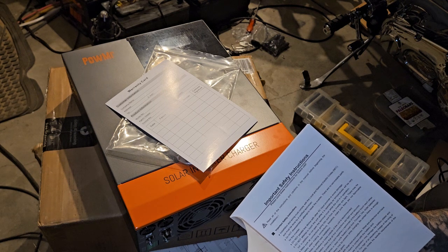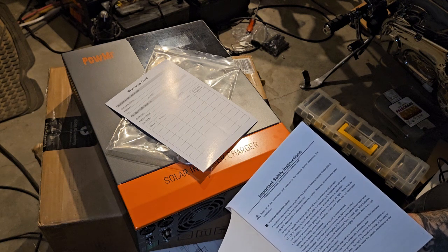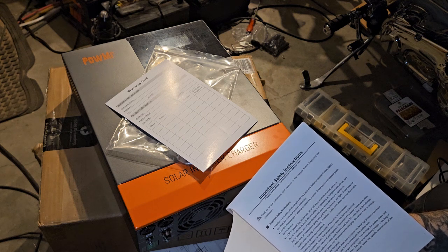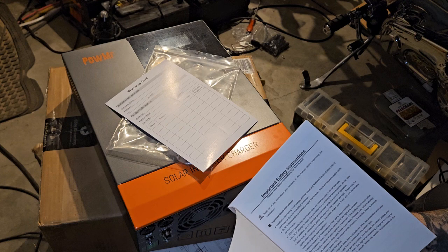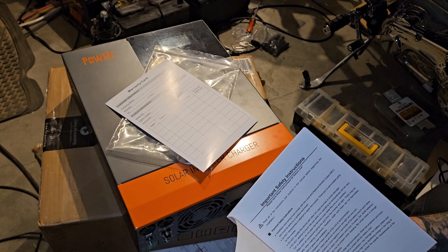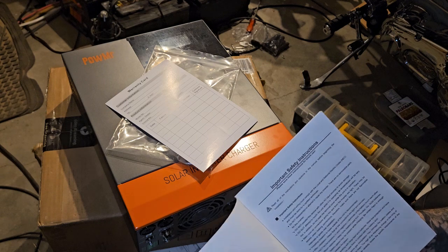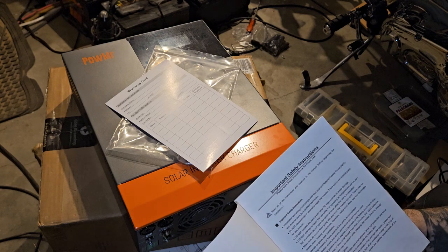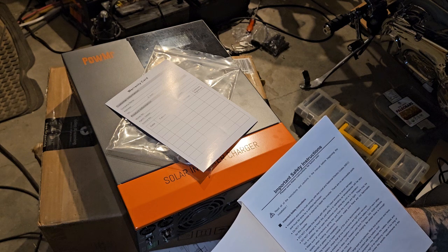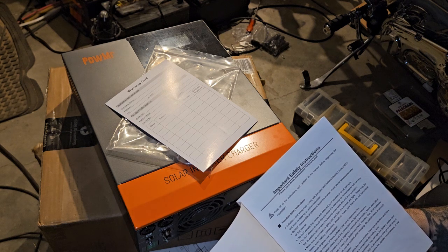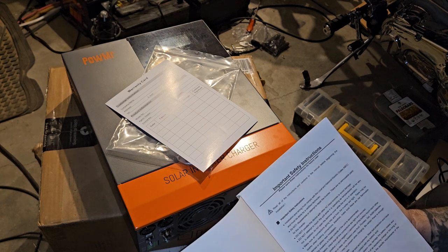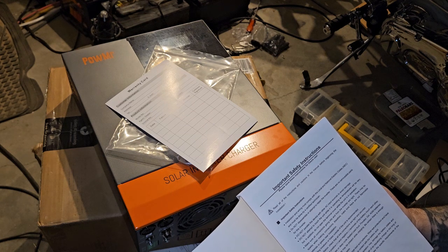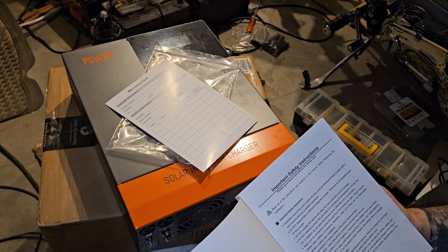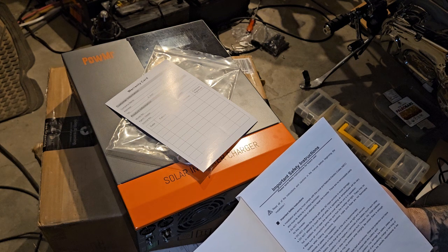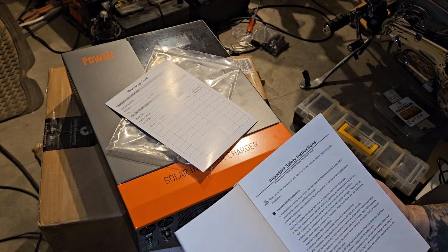Do not disassemble or attempt to repair the inverter. Do not parallel. Do not attempt to touch the unit while it's operating, as temperatures will be very hot. Lovely. In addition, do not open the terminal cover when the unit is in operation. Make sure all connections going in and from the inverter are tight. There may be sparks when making connections, therefore make sure there are no flammable materials or gases near the installation. Installing breakers or fuses outside of the unit is recommended. After installation, check all line connections are tight and secure. Do not let the positive and negative terminals of the battery touch each other.